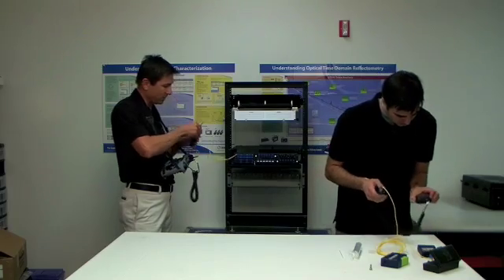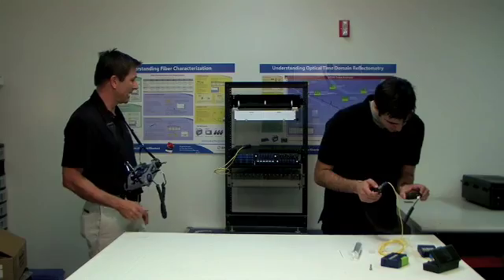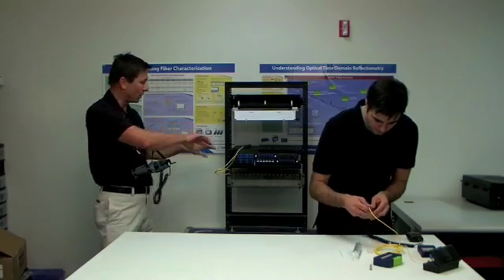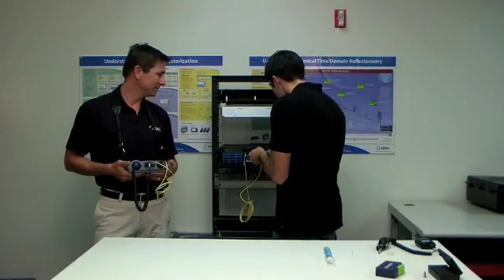Now, I've got a VFL pushing power, pushing visual light into the line. And this tool set gives me my hands back, so I'm able to open cabinet doors, or check through bundles of patch cords, or look for the fault on the line. Almost there? Almost. Almost there. Reading? Yeah, reading. All right. So, he's got his light level.